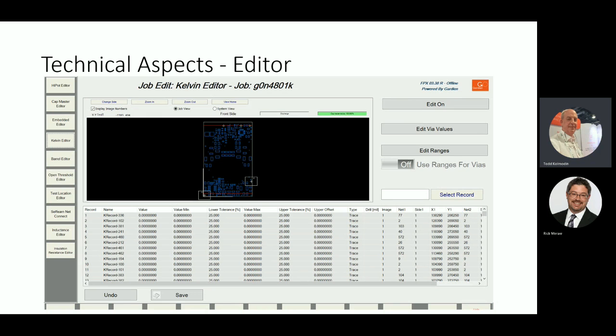Say you were reading 3.2 milliohms, and the board actually was, as you found through the testing process, better than that - down to 1.5 or 1.6 milliohm - you can go in here and make the adjustment without having to redo the whole learn master creation. Also, if you were able to supply the values up front once they're loaded in, any minor tweaking or changing of the upper and lower tolerances can all be done here.